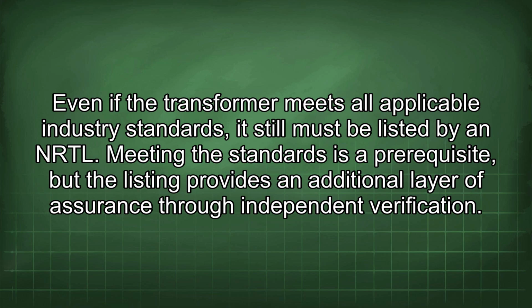Even if the transformer meets all applicable industry standards, it still must be listed by an NRTL. Meeting the standards is a prerequisite, but the listing provides an additional layer of assurance through independent verification.